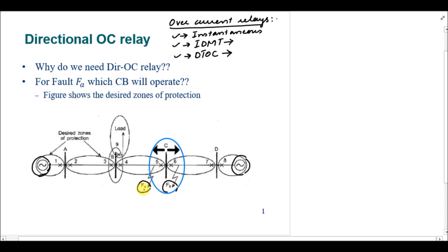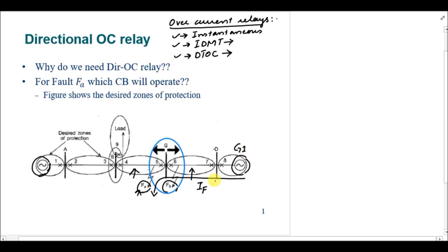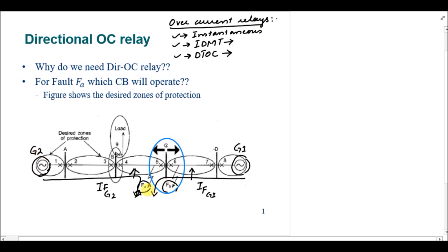FA is the fault occurring in this zone and FB is the fault occurring in line CD. In the case of fault FA, one part of the fault current IFG1 will be flowing from generator one, and the other part IFG2 will be flowing from generator two. So for fault FA, circuit breakers four and five should operate.